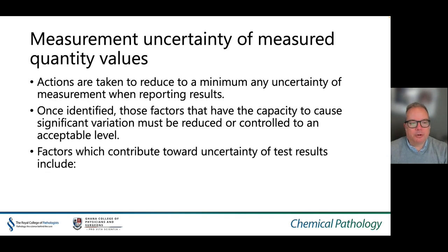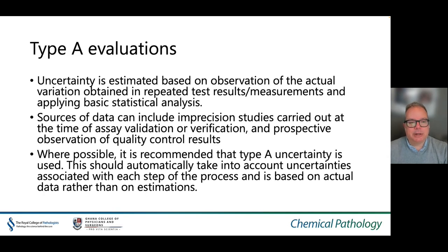Regarding measurement uncertainty of measured quantity values, actions are taken to reduce to a minimum any uncertainty of measurement when reporting results. Factors that have the capacity to cause significant variation must be reduced or controlled to an acceptable level. Factors which contribute to uncertainty include Type A evaluations, where uncertainty is estimated based on actual variation obtained by repeat tests or measurements and applying basic statistical analysis. Sources of this data can include imprecision studies carried out at the time of assay validation or verification, or prospective observation of quality control results. Where possible, it is recommended that Type A uncertainty is used as this automatically takes into account uncertainties associated with each step of the process and is based on actual data rather than estimations.